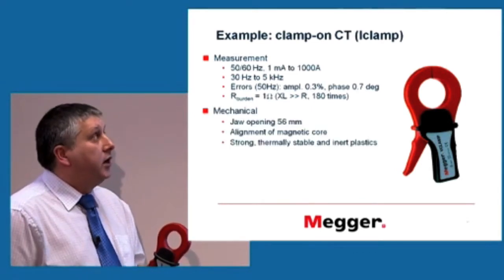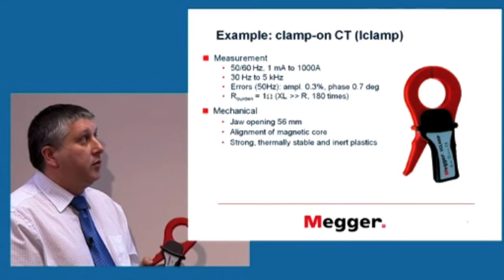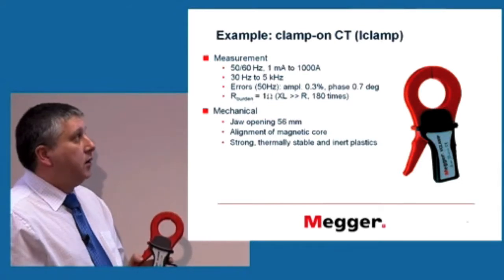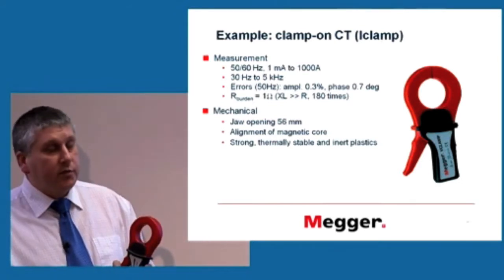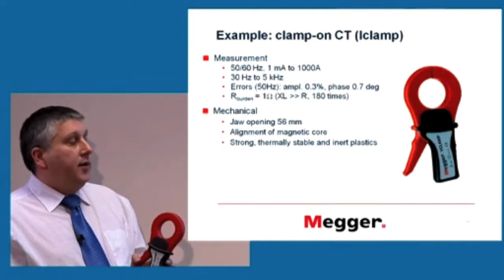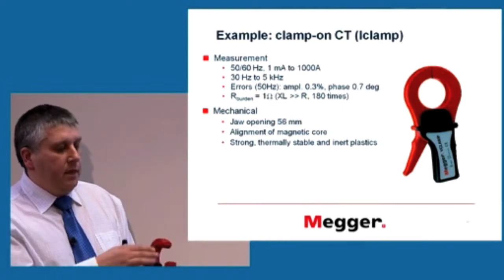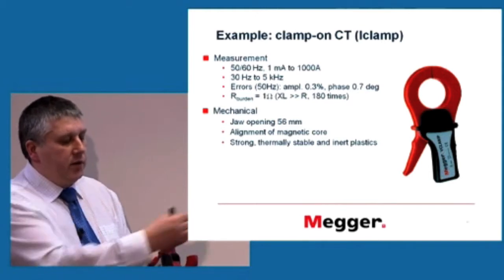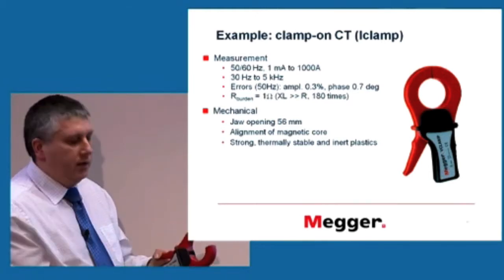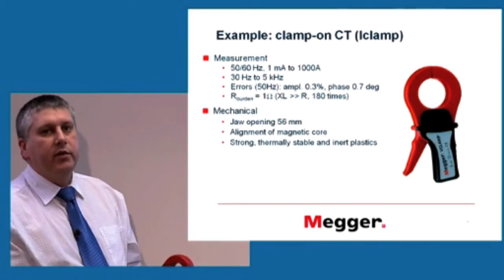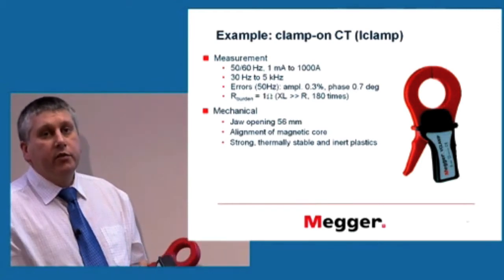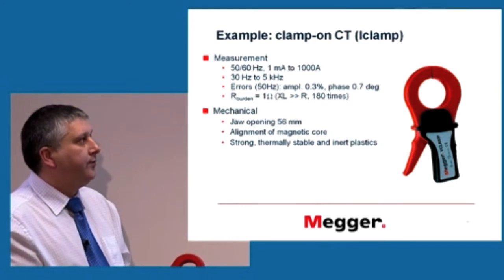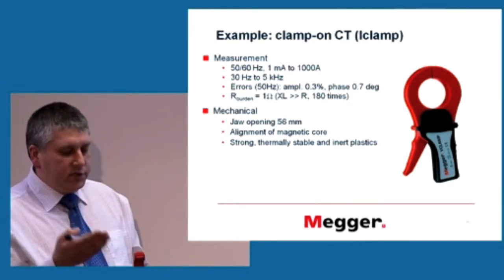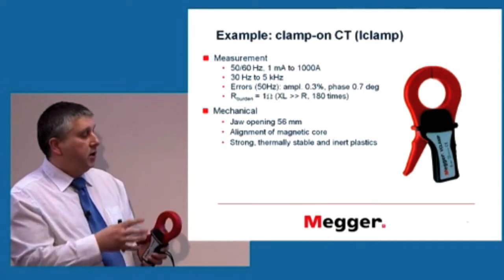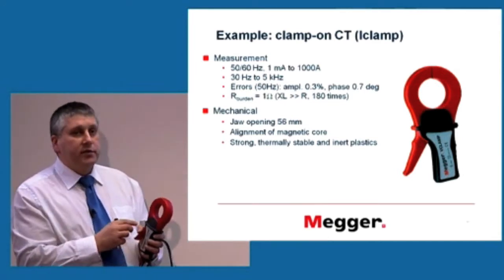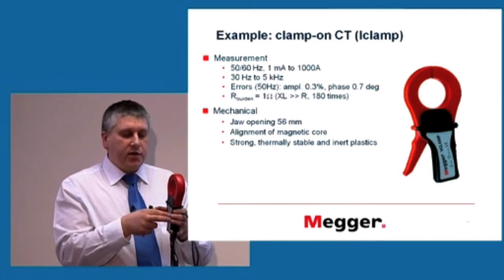But there are other requirements here, because obviously this is just a measurement. What else is required? A mechanical performance is required. If we want to clamp this around a conductor, the jaws have to open enough to be able to clamp around that conductor. If you open too little, we wouldn't be able to clamp around something which carries 1,000 amp, which we can see is not going to be a small wire. There's a magnetic core which is split, so as it closes, the mechanics of that clamp has to align that core such that it perfectly mates.